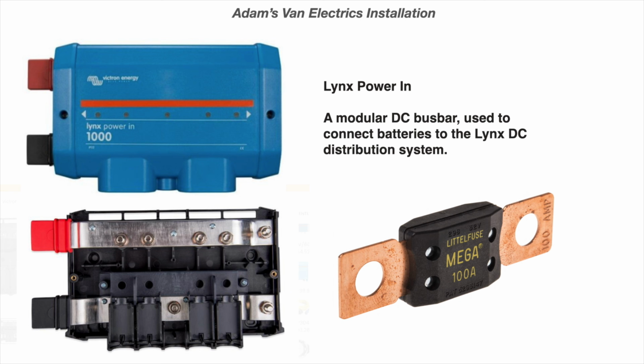So we also use the Victron Lynx Power In module. It's a busbar system. It accepts the mega fuses, the 100 amp and the 40 amps and so on. So this will start bringing down or giving you fault protection on a lower amount of current, and then we can distribute that to other things around the van.